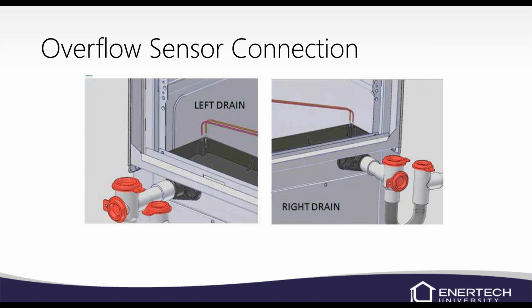And let me paraphrase that with, the trap has to have fluid in it. So if it's ran all winter and dried out that trap, and then in the summer it plugs up, you've got to have water in there, or it won't drain until the fan shuts off. It's the negative pressure coil, and it'll pull air through that drain. So make sure we have a trap on there.